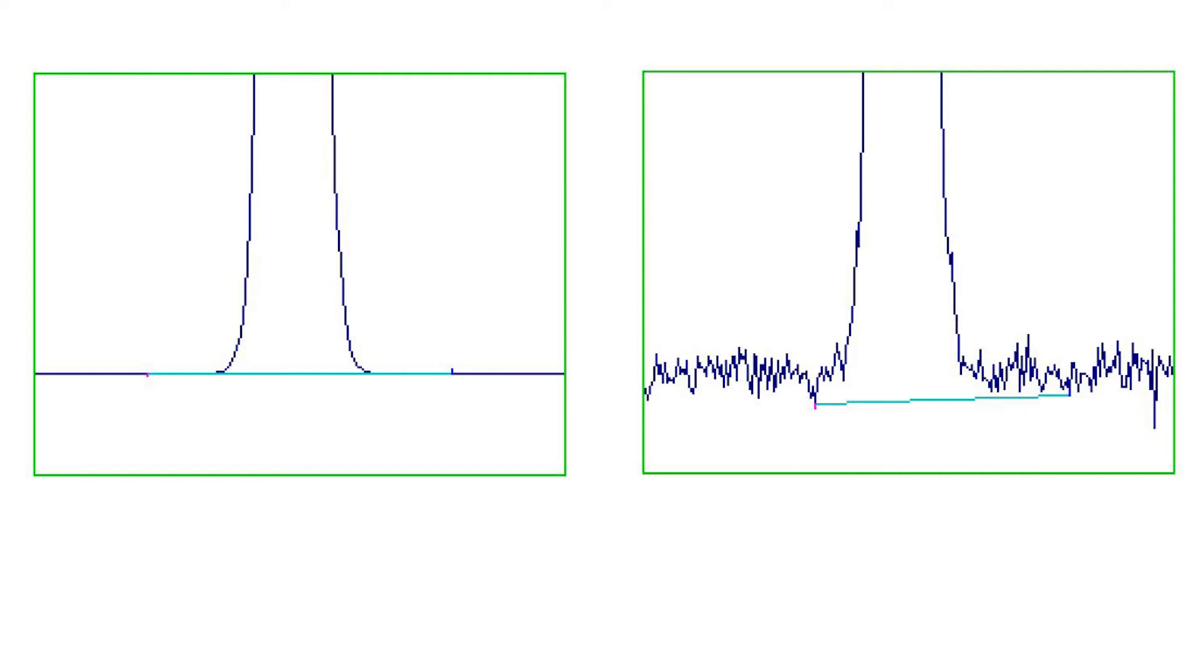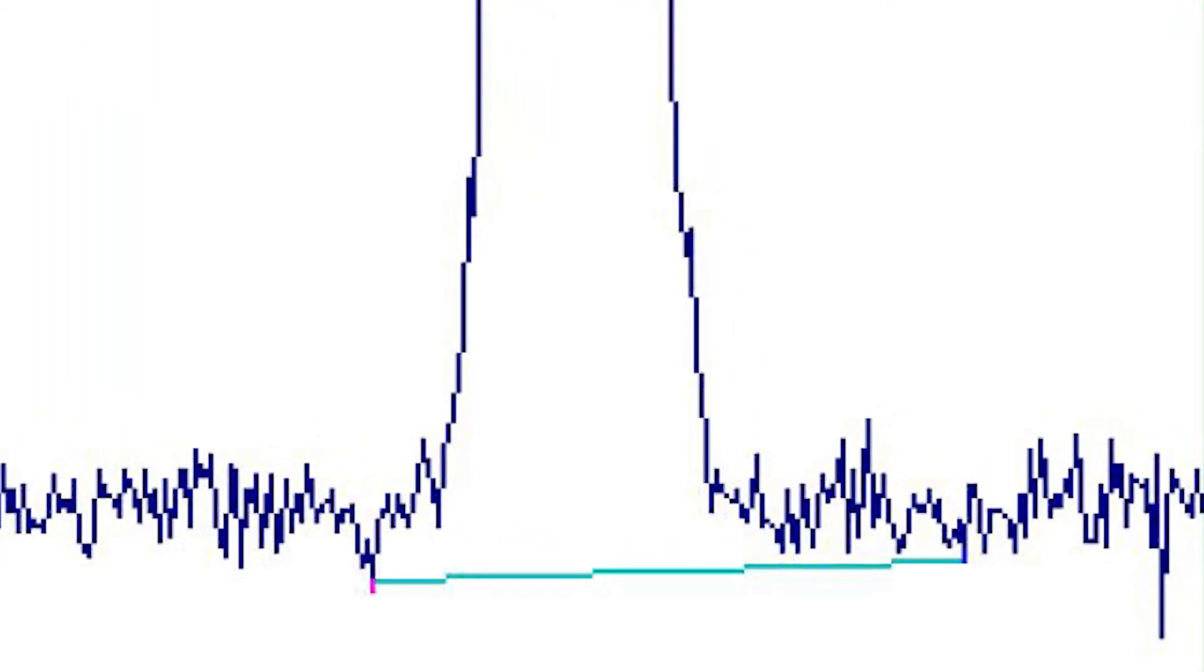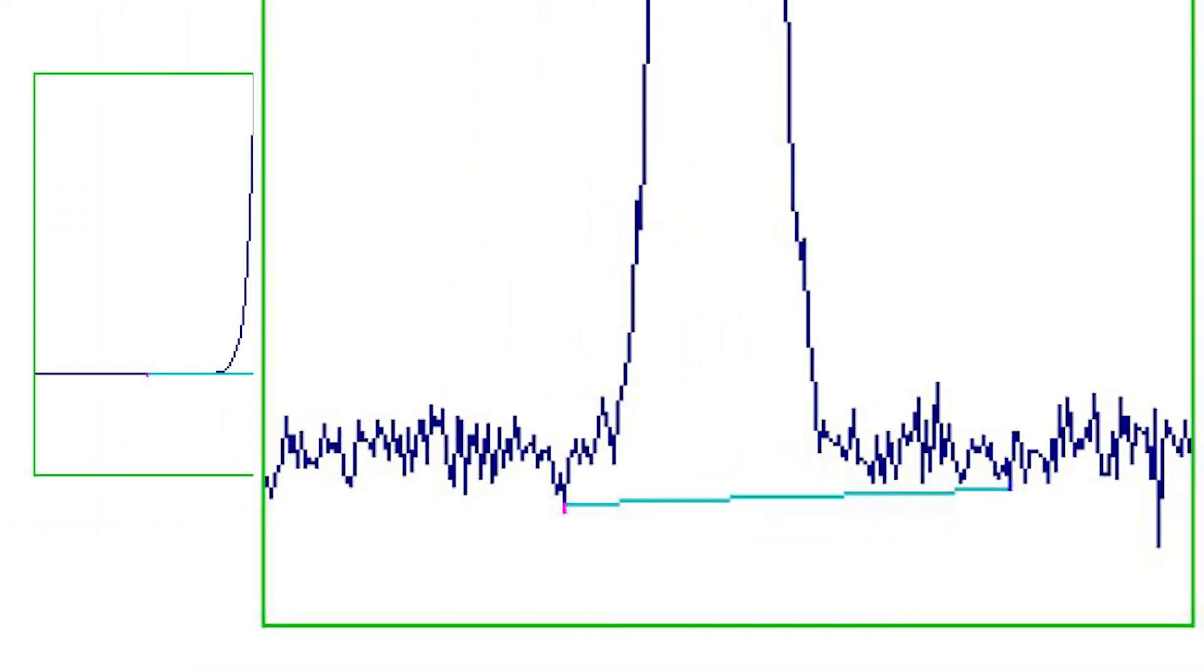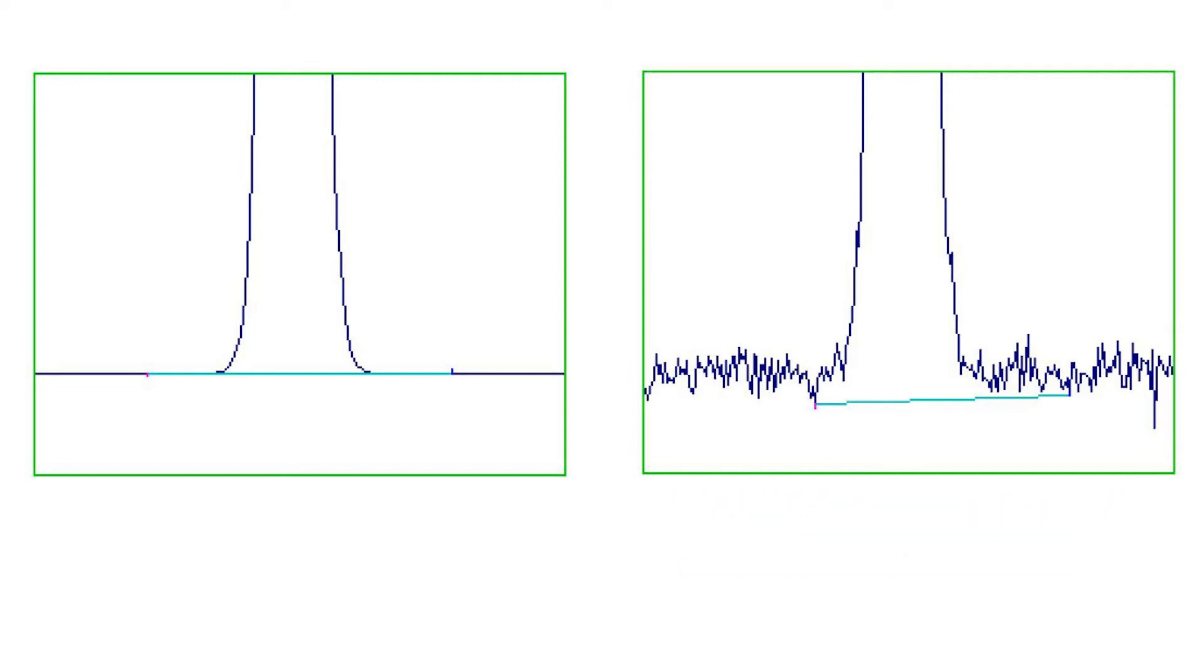Both effects are consequences of the peak integration algorithm, which contracts and lowers the baseline until the chromatogram trace does not penetrate it. On a noisy chromatogram, therefore, the baseline is drawn from one negative going noise peak to another. Altering the starting and ending points does not significantly affect the peak area or height, but lowering the baseline increases both the peak height and area. In this example, the height is increased by 8% and the area is increased by 17%. As the peak is integrated, noise near the peak top will affect the calculated height, and noise anywhere on the peak will affect the calculated area. However, these effects are less significant than those due to the lowered baseline.